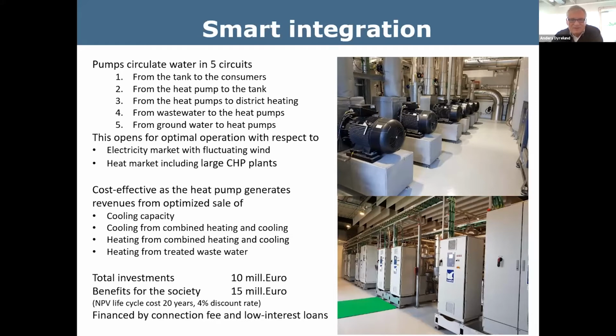Now comes the interesting part: when there's available capacity and not enough cooling demand, we can cool down the wastewater with the heat pumps. Treated wastewater is pumped to the plant and we cool it from 15 degrees to 5 degrees. The wastewater plant doesn't pay for that, but we can also say we extract surplus heat from the wastewater for free. It's very efficient since we already have the heat pumps available.